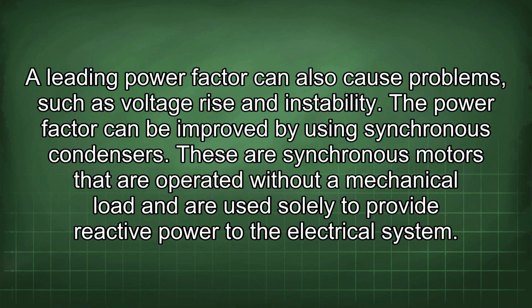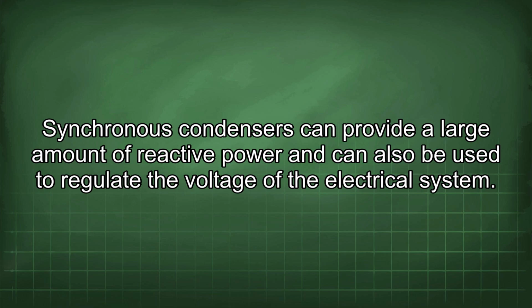The power factor can be improved by using synchronous condensers. These are synchronous motors that are operated without a mechanical load and are used solely to provide reactive power to the electrical system. Synchronous condensers can provide a large amount of reactive power and can also be used to regulate the voltage of the electrical system.